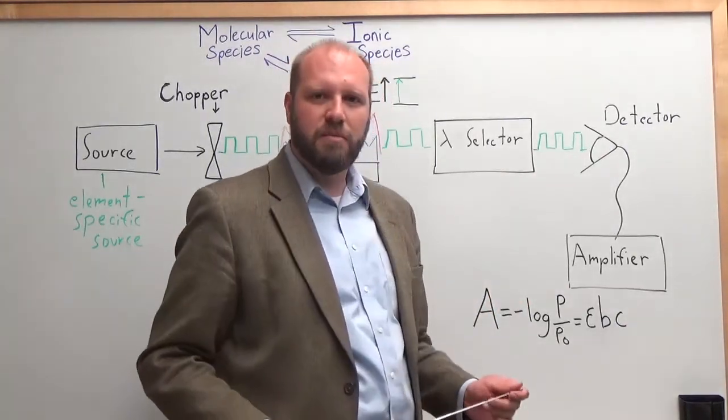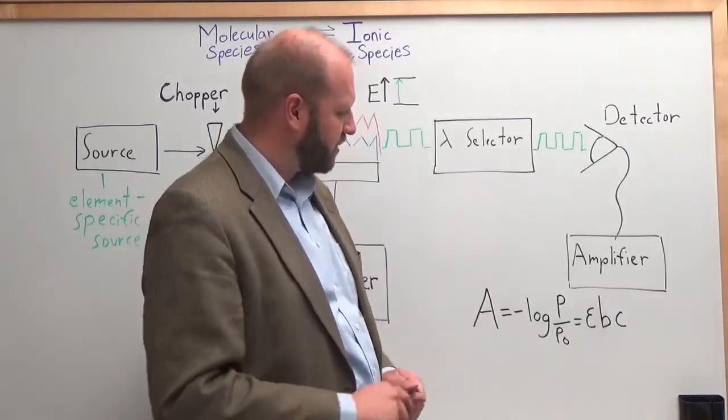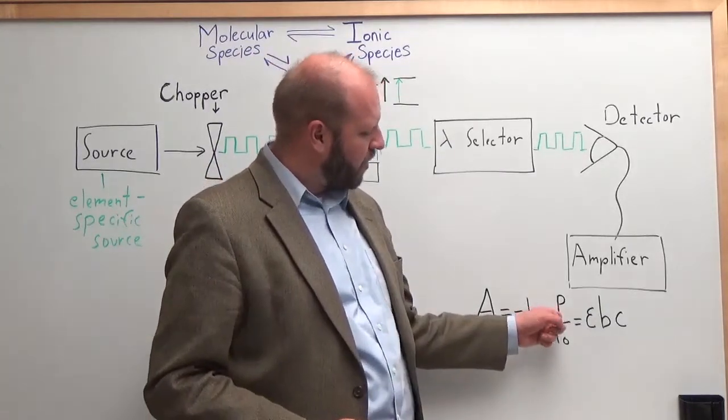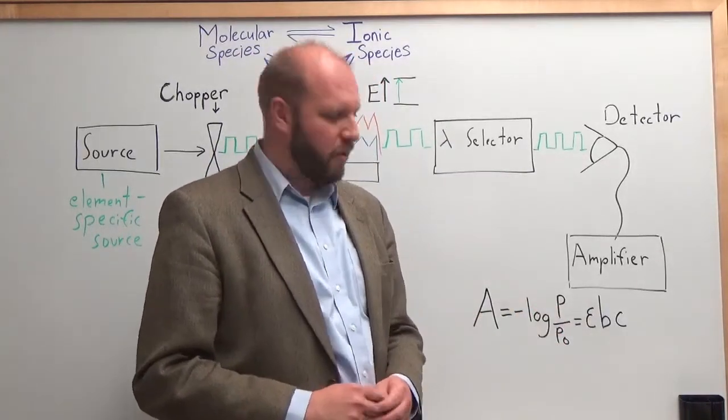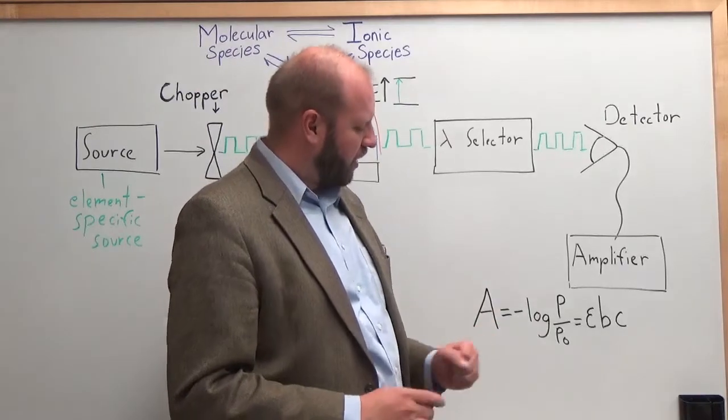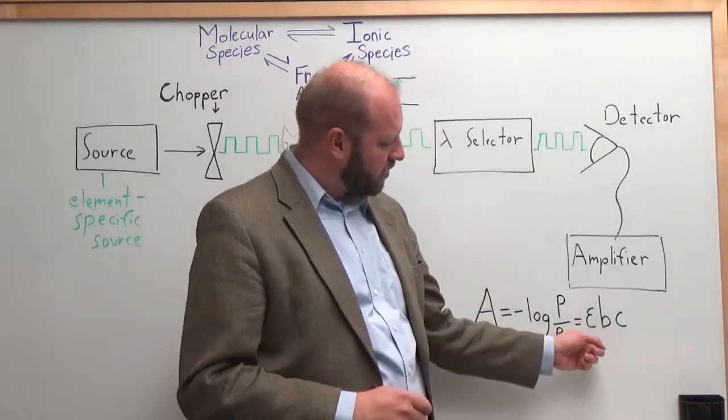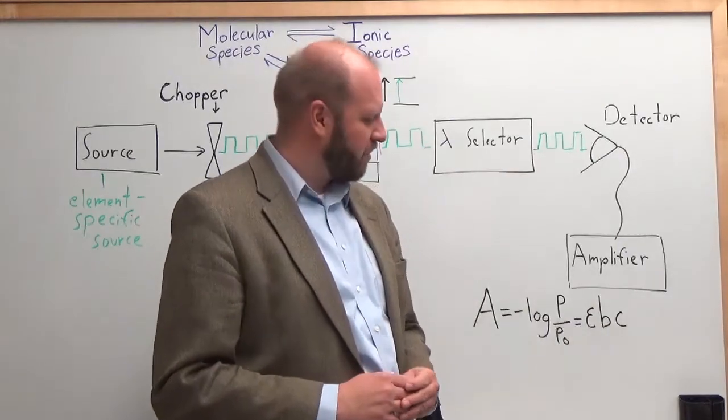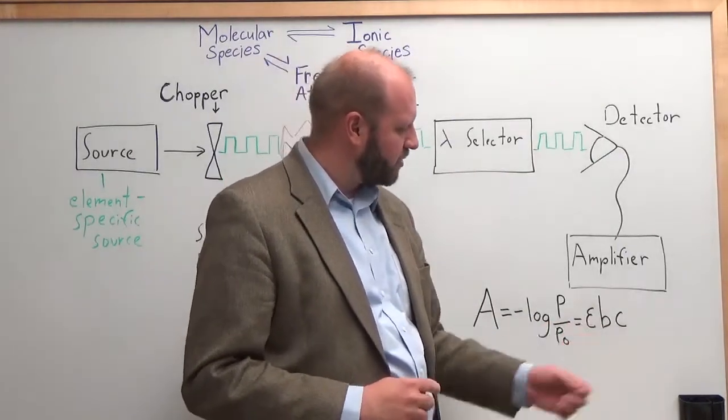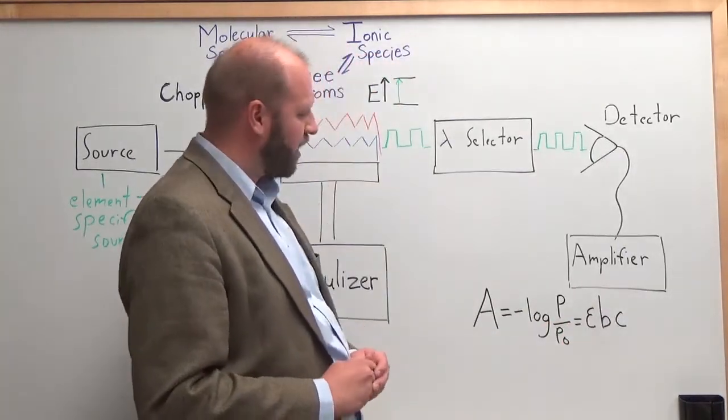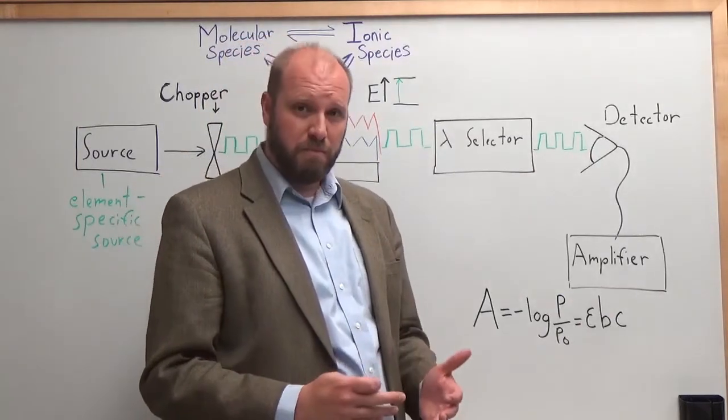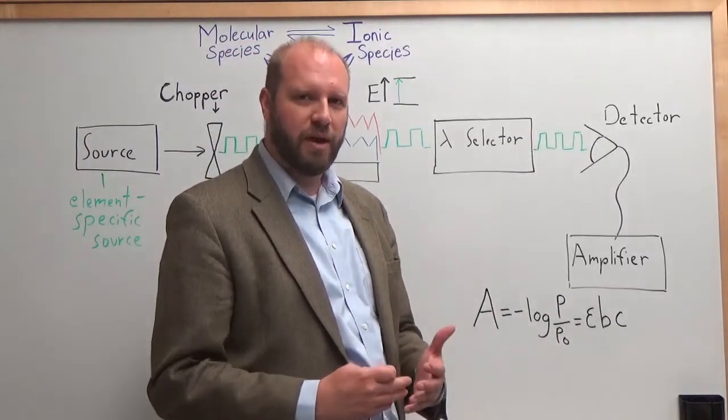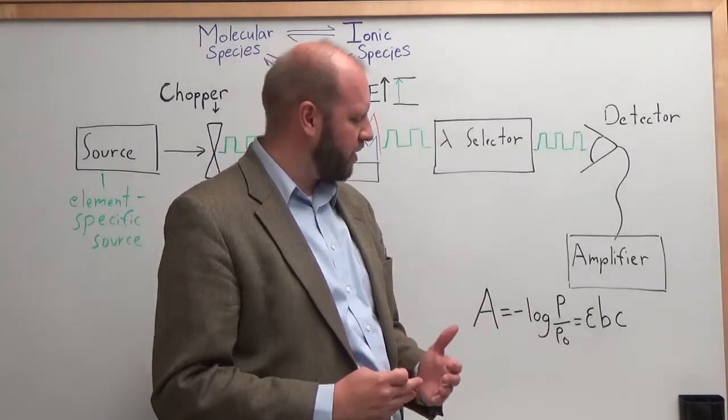And we use Beer's Law to measure the absorbance for this system. We measure the power versus the initial power in for our lamp source to relate to measure the absorbance. And this is equal to epsilon B C where epsilon's molar absorptivity, B is my path length and C is my concentration of my free atoms in the flame. I can make a measurement for an unknown and use a calibration curve I generated from standards to figure out what my unknown concentration was for my element of interest.